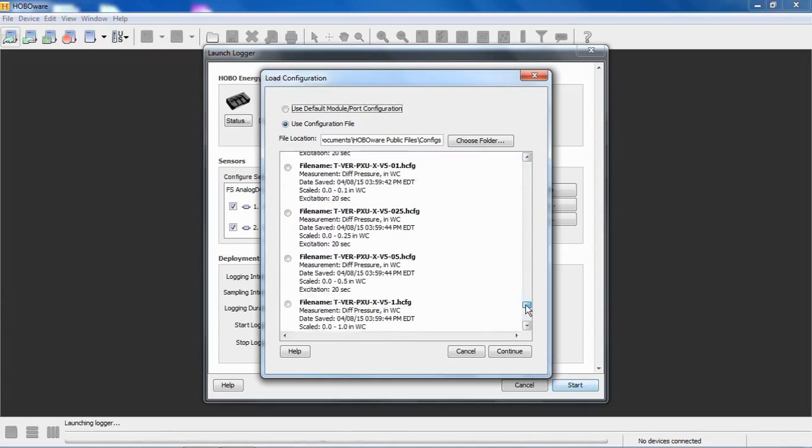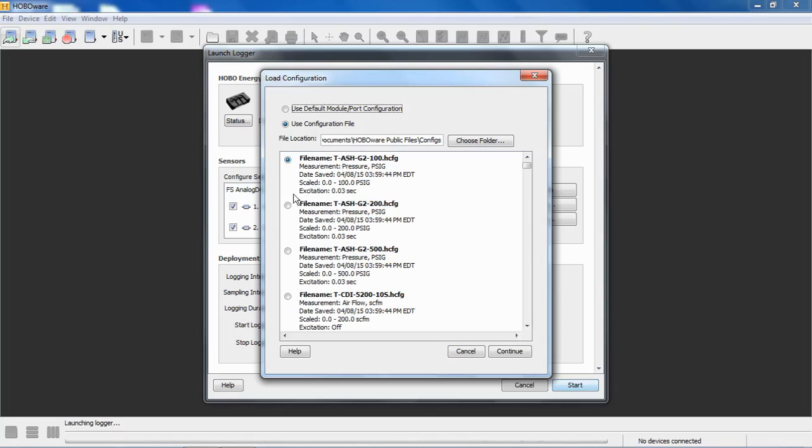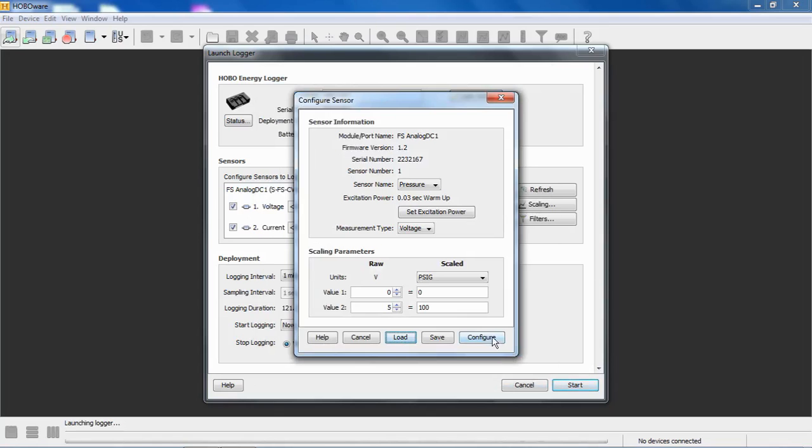And these are all pre-configured configurations for those sensors. So it includes, for example, this one here is a 100 PSIG gauge pressure transducer. So this gives you the ability to, if we selected this, it will scale it as 0 to 100 PSIG. And it will turn the excitation on to the manufacturer's recommended excitation of 30 milliseconds. So if I click on this one, if I say, okay, this is the sensor I have connected, and I click on continue, notice my scaling and everything is all set. I have a sensor name called pressure. Here, I have my excitation turned on with a 30 millisecond warm-up time. My voltage type is set correctly for 5 volts, because this is a 0 to 5 volt output sensor.